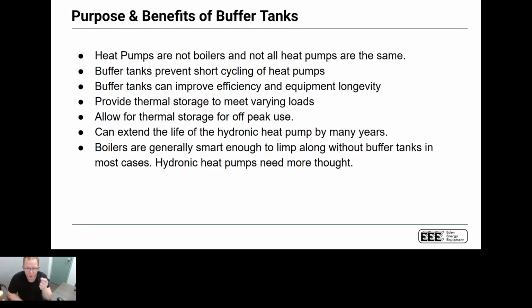The other thing is that the buffer tank can improve efficiency and equipment longevity. We don't want the heat pump banging on and off all the time. It's not good for the system. Technically, a buffer tank could also provide some thermal storage, some thermal inertia within the system, especially if you have different loads. You may, in fact, have one room that only needs 4,000 or 5,000 BTUs. The buffer tank makes sure that your 5-ton heat pump, which would be heating the whole home at design and using all 5 tons, has a place to put that extra energy, so the heat pump runs for a minimum of 10 minutes so that we're not just banging on all the time.